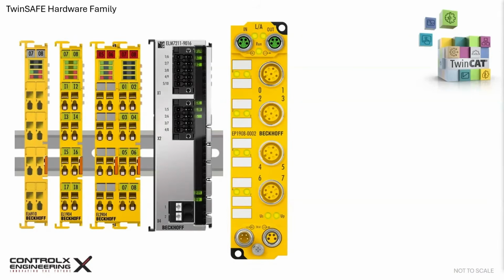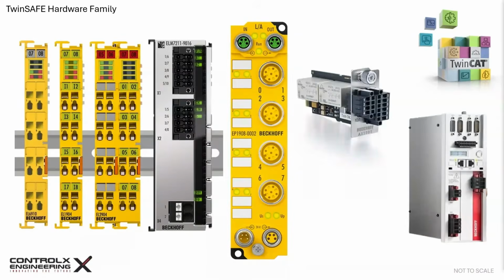Next, we have specialized devices with built-in TwinSAFE logic, like this single-channel drive for 48-volt servo motors. It features integrated TwinSAFE logic for safe torque off and safe stop 1 safety functions. Speaking of motion devices, Beckhoff also offers optional safety modules, like this AX5801 option card for the AX5000 series servo drives, which enables the implementation of safety-relevant drive functions like STO and SS1. There are many more TwinSAFE devices in other form factors, but here I have listed the most common device types.